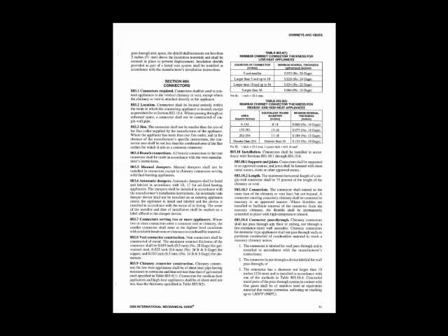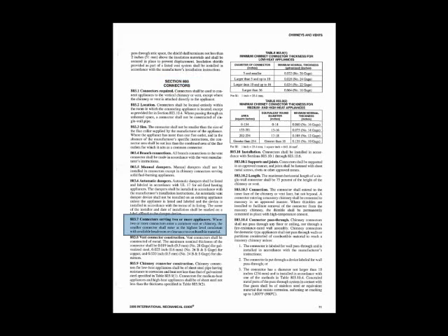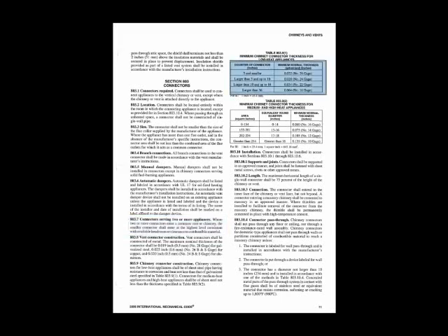Section 803 talks about the connector. The connector is the piece of pipe that goes from the appliance to the chimney or vent. It is a little piece of connection. It talks about connectors serving two or more appliances. Talks about what type and what type of sheet metal gauge you must use for the different connectors. Notice, 5 and smaller is 26 gauge. Larger than 16 inch diameter is number 16 gauge. The lower the gauge number, the thicker the metal, the stronger the vent will be.